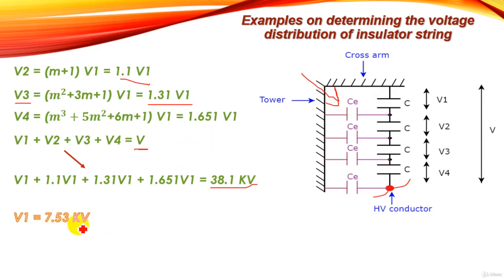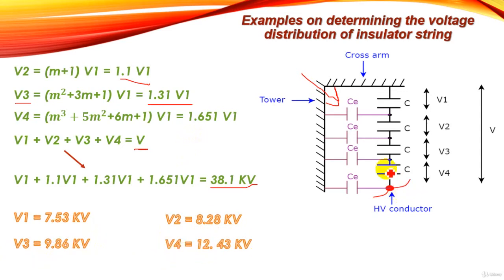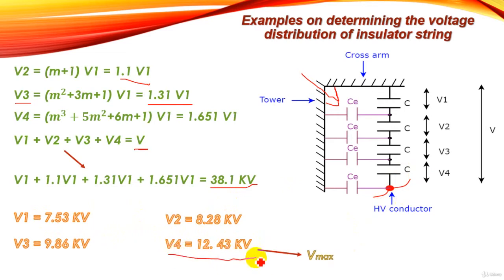Solving gives: V1 equals 7.53 kV, V2 equals 8.28 kV, V3 equals 9.86 kV, and V4 equals 12.43 kV across the lower unit. We can observe that the maximum voltage occurs across the lower unit — the unit closest to the high voltage conductor. Considering stray capacitances, the voltages across each unit are not equal.